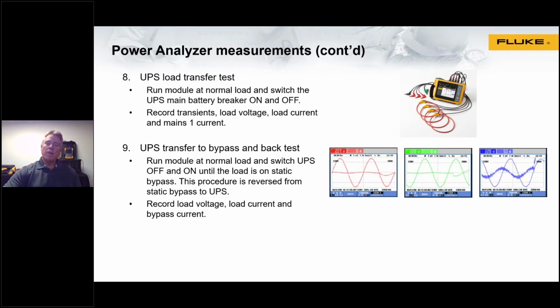Then on an ongoing basis, periodically, could be monthly or quarterly, you would want to conduct maintenance tests throughout the life of your overall contingency supply system. You'd follow the combined test procedure for really everything except the standby generator. Generally, the recommendation is that it only needs to be tested once per year.